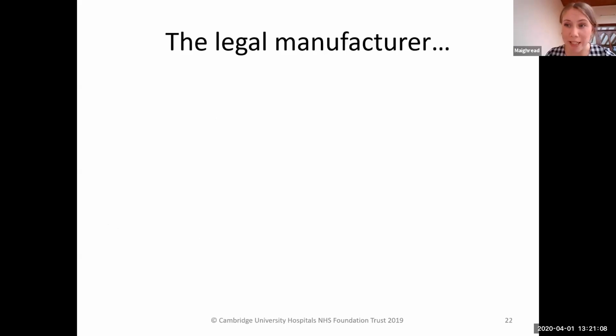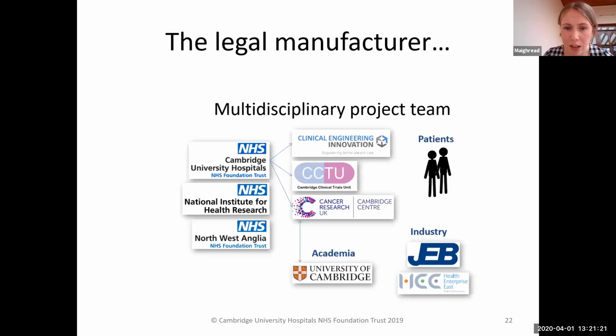Another conformance issue which sometimes arises is the legal manufacturer. With all handover documentation, a legal manufacturer must be stated for a device. With some of our projects, the team involved can be quite large, and there can be several bodies taking on different roles.